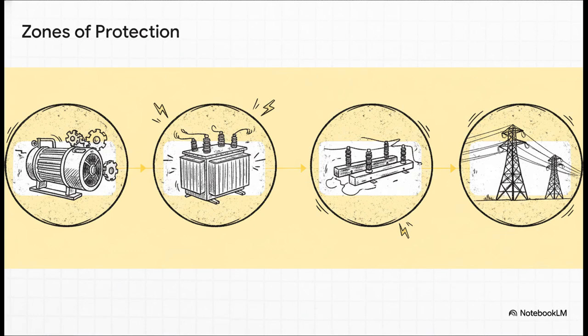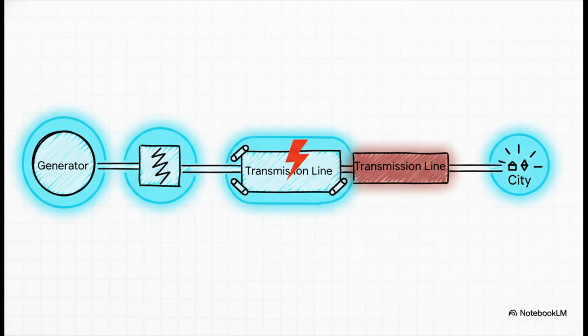The system creates what are called zones of protection around every single major piece of equipment. Each generator, each transformer, each transmission line, they're all inside their own little protective bubble, constantly being monitored. And these zones even overlap, so there are absolutely no blind spots. And the precision here is just amazing. If a fault happens in, say, the transmission line zone, the relays for that zone tell only its dedicated circuit breakers to open. The rest of the grid keeps humming along like nothing ever happened. This is what prevents a single failure from taking down an entire city.